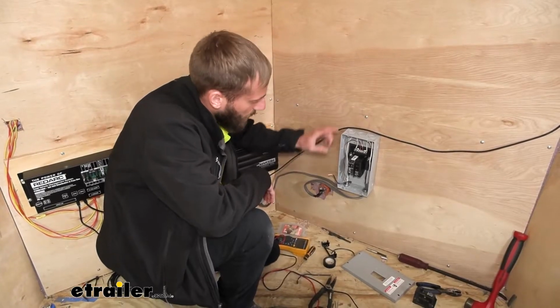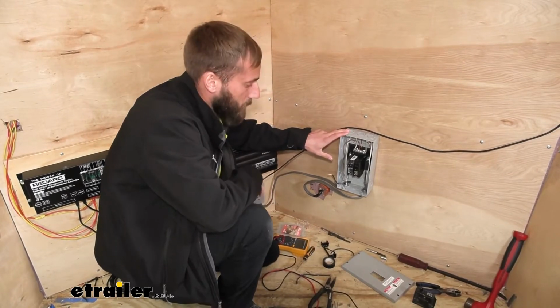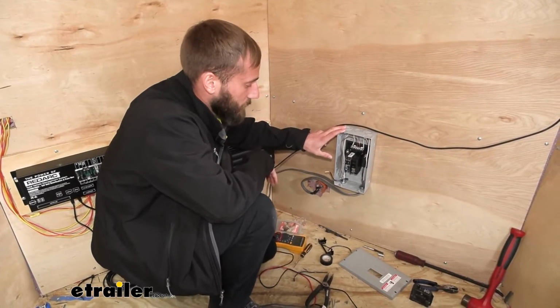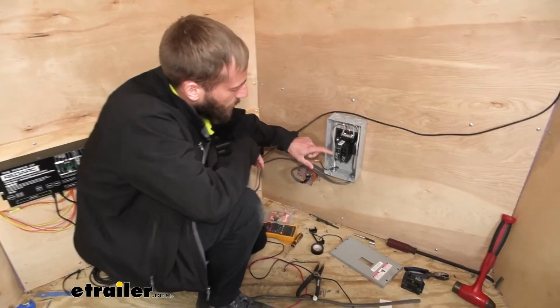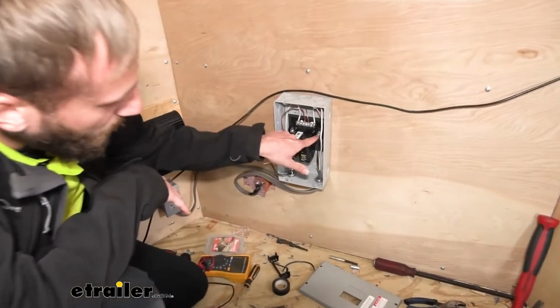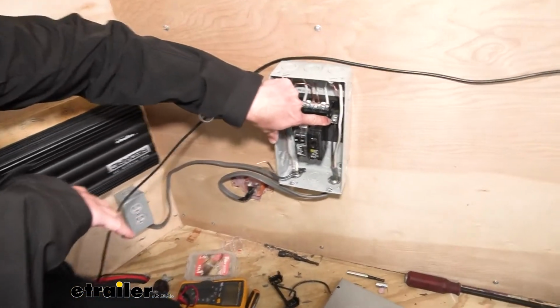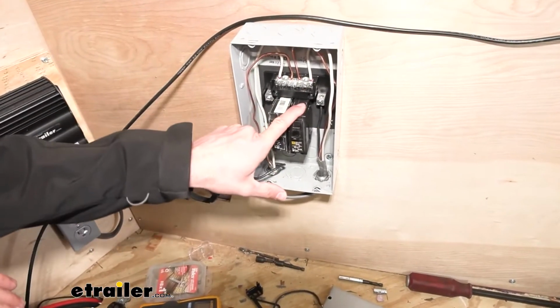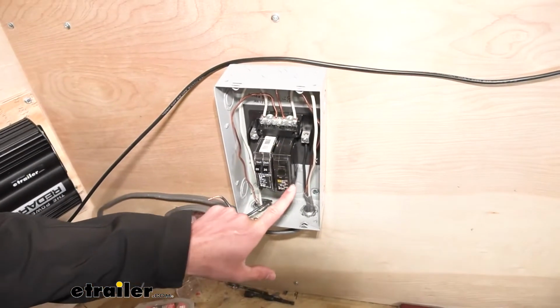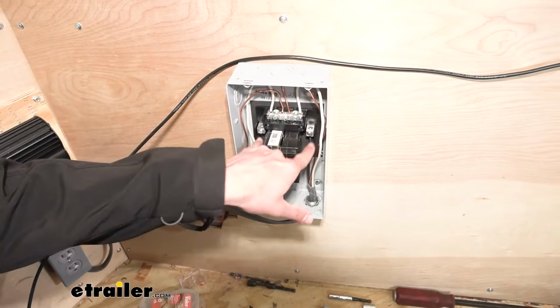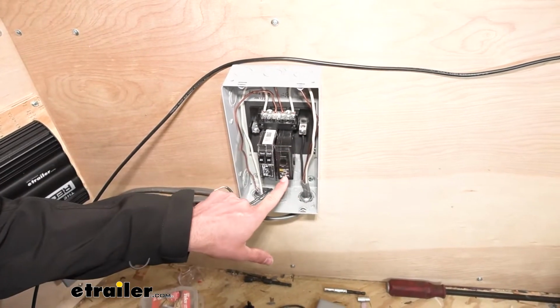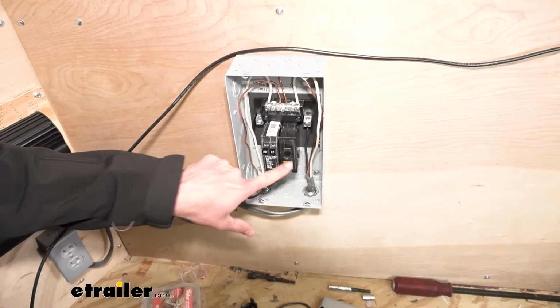So we realized after installing this that we don't actually have a main on here, and I do want to have a main just for safety. So what we're going to do is take our power, which we already have hooked up to this leg right here, so that's going to power this 30 amp breaker, which we're going to use as our main. Because these two legs are separate, I'm going to run a power wire over from our 30 amp on the screw down here over to my leg up here.